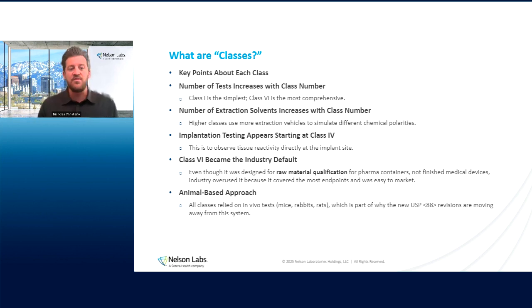And as I mentioned, we also see an increase in the number of extraction solvents, typically with each class identification as well. So following that nomenclature, higher classes would use more extraction vehicles to simulate those different chemical polarities and so on. Implantation testing, we typically have seen starting around class 4 as well. This is to observe tissue reactivity directly at the implant site. We'll talk a little bit more about why that test has seemed pretty irrelevant in historical use, given the fact that we are testing materials and not finished goods, and also typically materials that are not implanted.